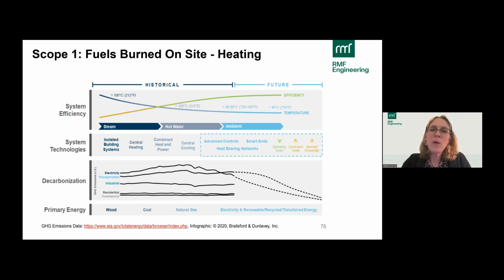On heating, what we're seeing is heating systems used to run on steam. In about the mid-20th century, if you were building a brand new district energy system, you might build it with hot water, because you could pump hot water now. You have a pretty good electrical grid. Back in the late 1800s, the electrical grid was pretty shaky, so you didn't have a lot of pumping power, but steam propels itself. So it made sense to put steam in a pipe and send it out to 5, 10, 20, 30 buildings.